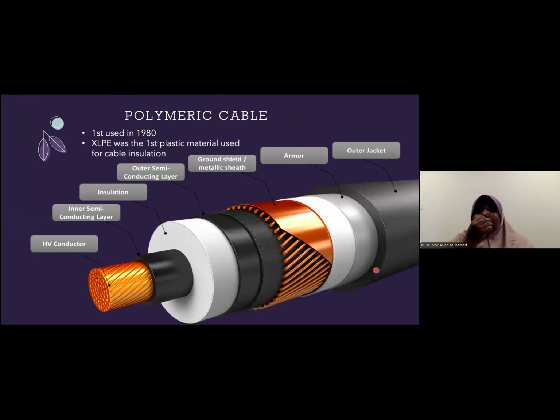So this is the construction of the polymer cable. This is the conductor. If you can see, the conductor is a small area. The largest area is the insulating system. We have the conductor to carry the current. We have the inner semiconductor layer. Then we have the insulation layer. This is the XLPE, LDPE, or other type of polymer.